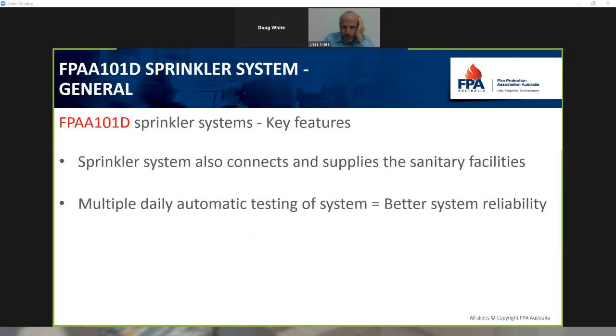Sprinkler system connects to the toilet, which you explained. We'll get into detail a bit in a second. There is a significant increase in reliability in the fact that we're now using the drinking water to supply our sprinkler system. It's an advantage from a reliability point of view because if that drinking water, for whatever reason, is switched off or reduced, we're going to know about it. And we're going to know quickly, and we're going to have to repair it quickly.